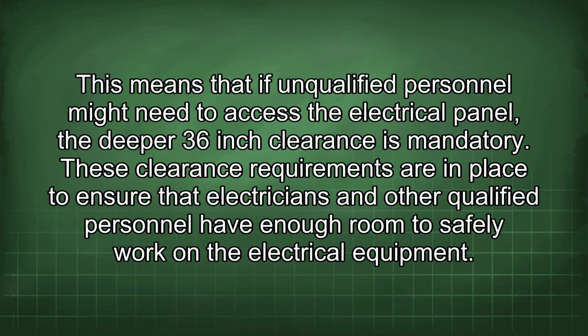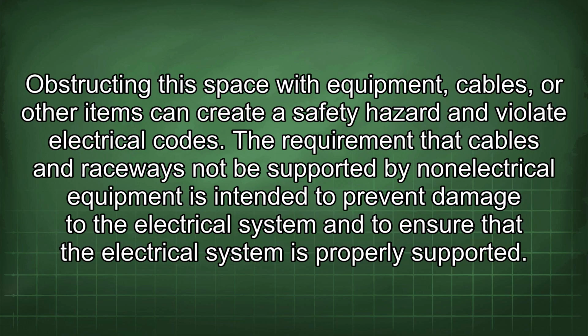This means that if unqualified personnel might need to access the electrical panel, the deeper 36-inch clearance is mandatory. These clearance requirements are in place to ensure that electricians and other qualified personnel have enough room to safely work on the electrical equipment. Obstructing this space with equipment, cables, or other items can create a safety hazard and violate electrical codes. The requirement that cables and raceways not be supported by non-electrical equipment is intended to prevent damage to the electrical system and to ensure that the electrical system is properly supported.